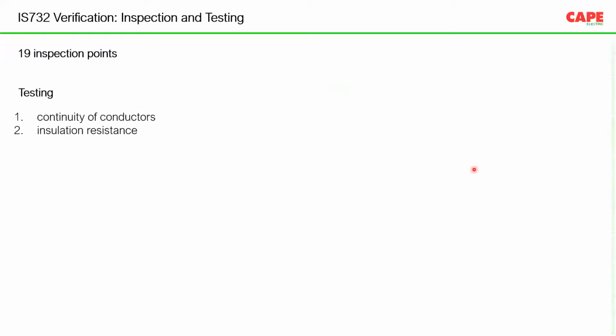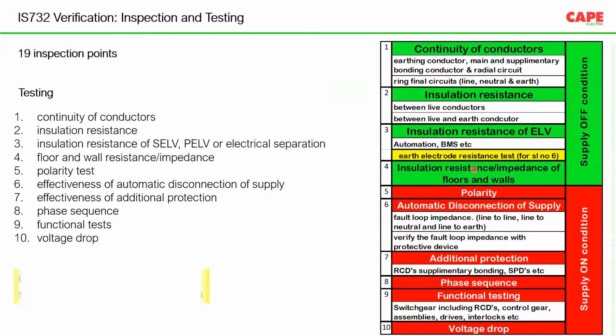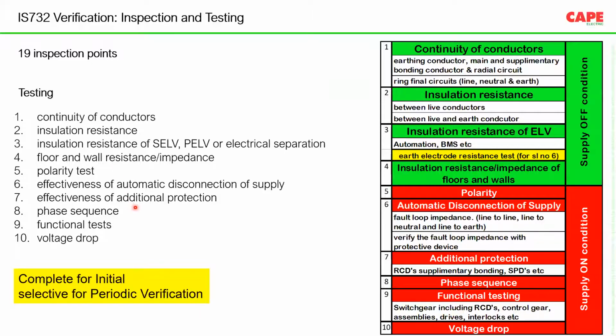Now I go to the last part of the presentation, the testing of an installation. How to ensure that your electrical installation is safe. IS 732 recommended 19 inspection points. There are 19 points which you are supposed to inspect. It starts with what is the philosophy with which electric shock is handled, what is the philosophy with which fire and power sourcing plus fire barriers are installed, what is the philosophy with which over voltages are limited, what is the philosophy with which the wires are sized, like that. There are 19 inspection points.